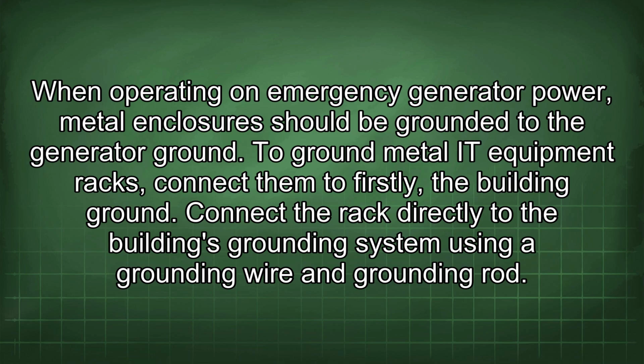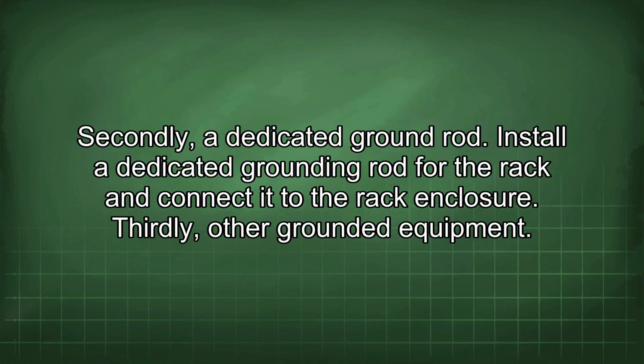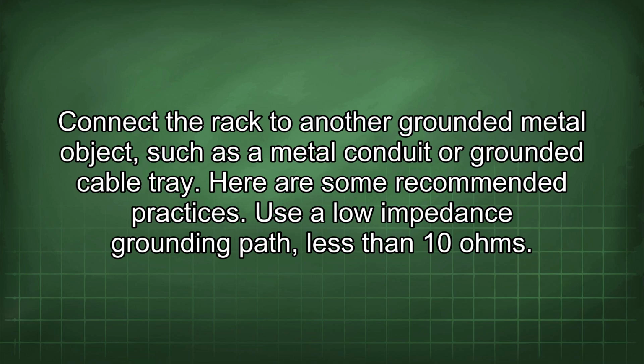To ground metal IT equipment racks, connect them to, firstly, the building ground. Connect the rack directly to the building's grounding system using a grounding wire and grounding rod. Secondly, a dedicated ground rod. Install a dedicated grounding rod for the rack and connect it to the rack enclosure. Thirdly, other grounded equipment. Connect the rack to another grounded metal object, such as a metal conduit or grounded cable tray.